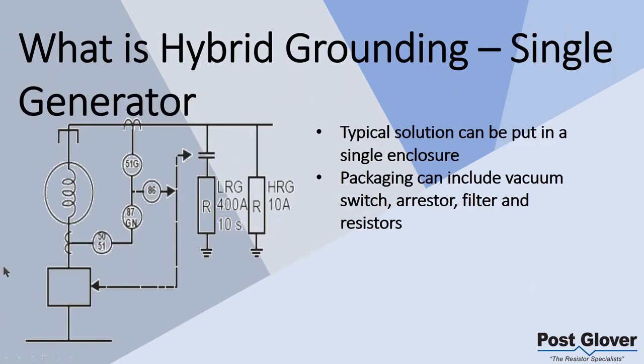And so here's an example of a drawing. This is a single generator. You have your generator with some relays, which we'll go into in a minute, but you basically have a low resistance ground resistor in parallel, and like I mentioned before, 400 amps is a very common current rating, and 10 seconds is a very common time rating. Then the high resistance ground is 10 amps here. So those are in parallel.